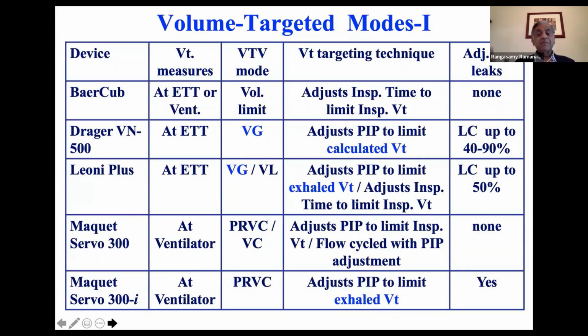Again, just like in the pressure control mode, many ventilators operate differently. You need to know, I asked Ursula to tell me what ventilators you commonly use in Romania, and there are a number of them: Draeger, Leoni Plus, Maquet, Servo I. So you need to know your machine, again. Each one does it differently. Here is BaerCub, they measure at the endotracheal tube or at the ventilator. Draeger measures only at the endotracheal tube, Draeger and VN-500, because they calculate and estimate the tidal volume based on the amount of gas going in and coming out. So in their volume guarantee mode, okay.